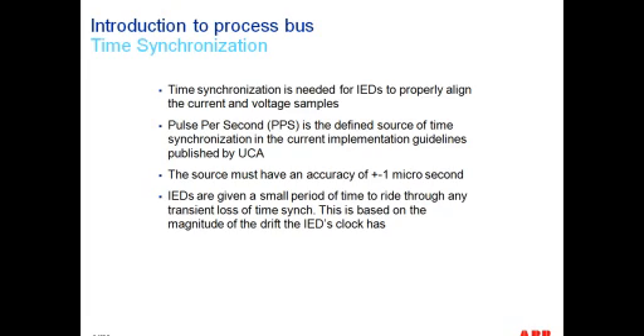When we talk about time synchronization, as we've discussed, it is definitely needed to properly align the current and voltage samples. What the UCA implementation guidelines prescribe today is 1 PPS, which stands for pulse per second. The source of synchronization must have an accuracy of plus or minus 1 microsecond. And without getting into too many details, the IEDs are given a small period of time to ride through any transient loss of time sync. This is based on the magnitude of the drift of the IED's clock.